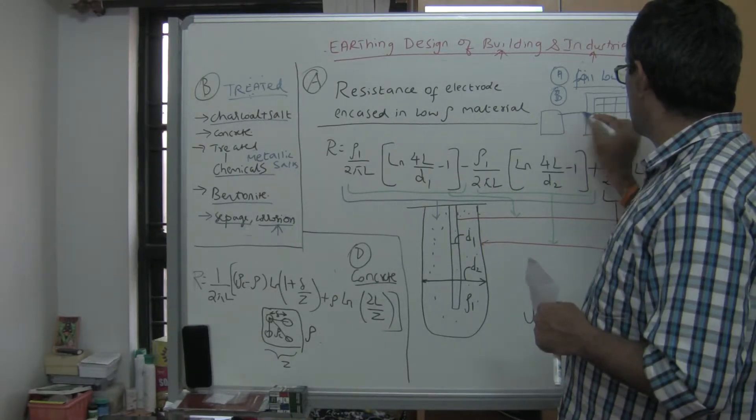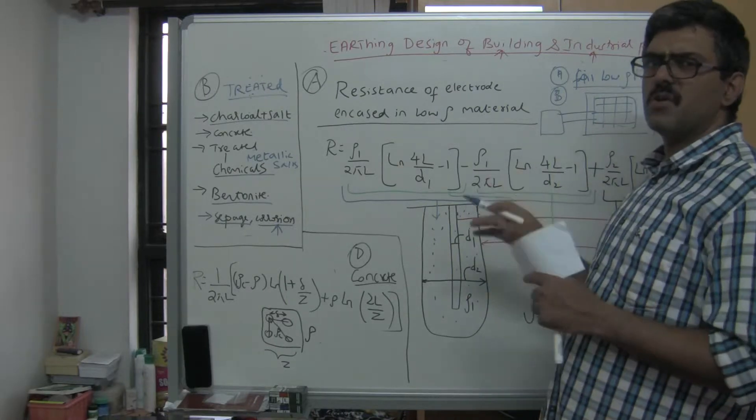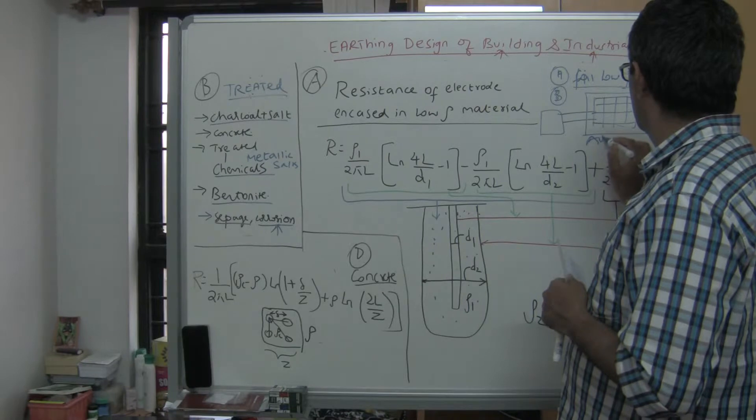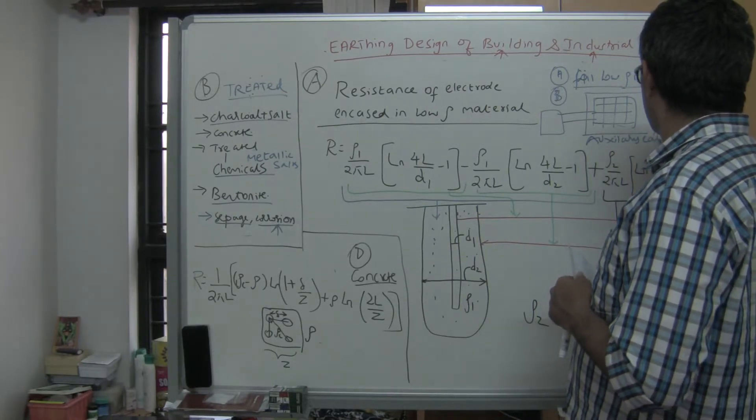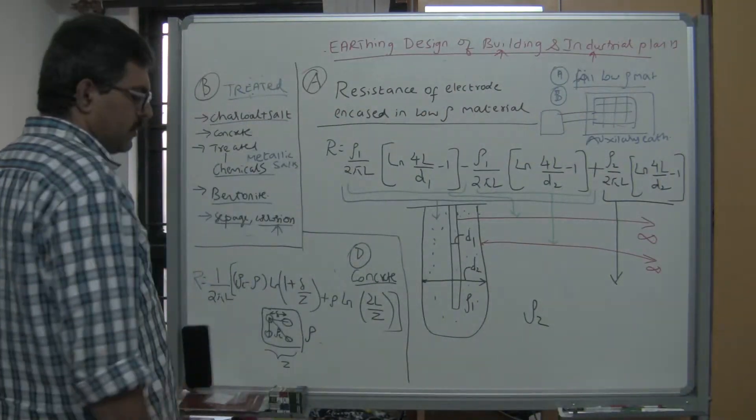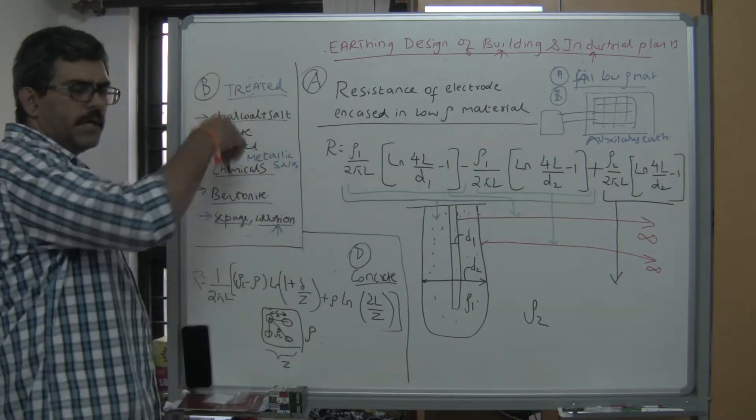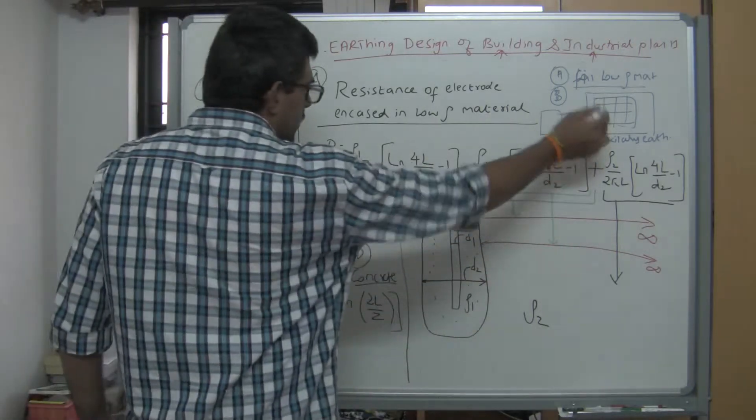Connect the earth grid here to a separate earth grid remotely - this is called an auxiliary earth mat or earth grid. So whenever you have high resistivity, one option is to go for a treated earth pit, and another option is to go for an auxiliary earth grid.